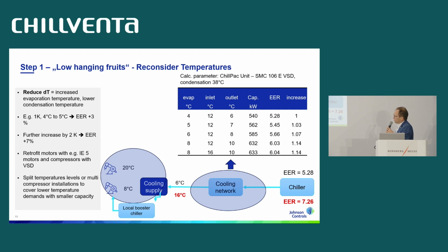If you retrofit further your motors with a higher efficiency motor or the compressor with a variable speed drive, you can gain another 10% of efficiency increase. And if you split temperature levels or do multi-compressor installations to cover low temperature demands, there is another option to increase massively. For example, the energy efficiency ratio can easily increase to 7 if you provide your cooling network at higher temperature level and install local booster chillers for the real low cooling demand.